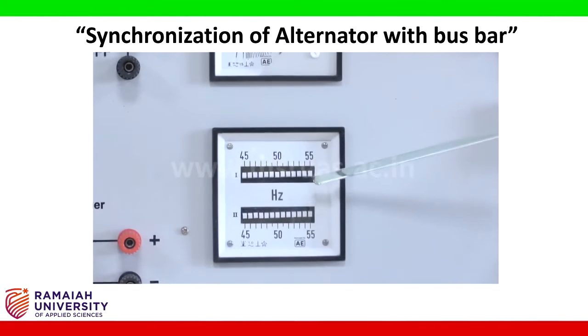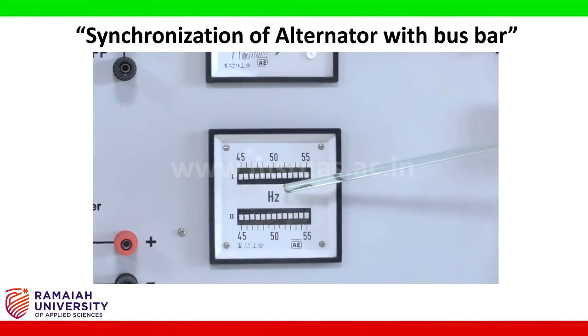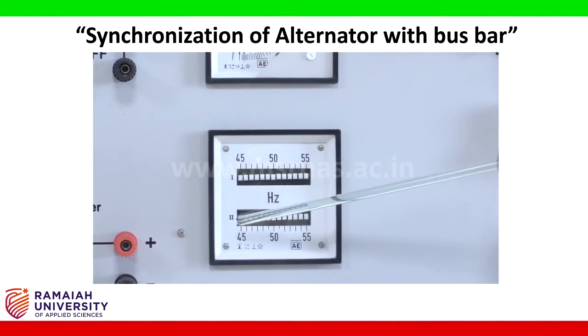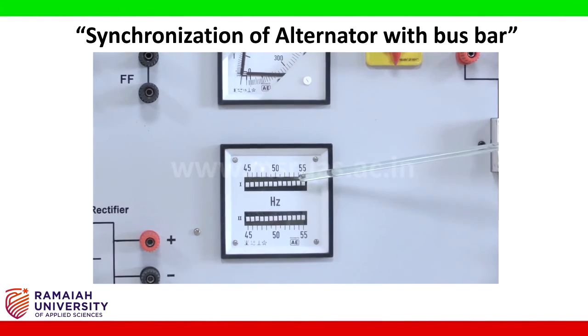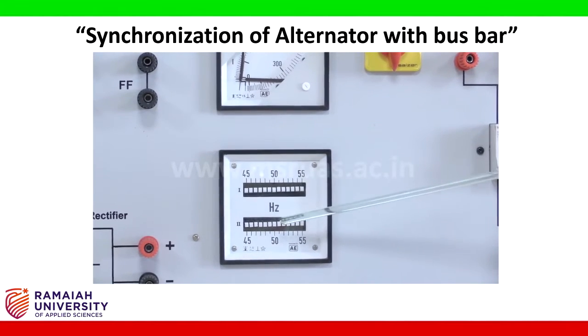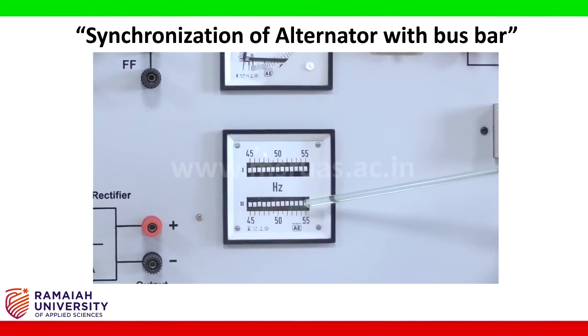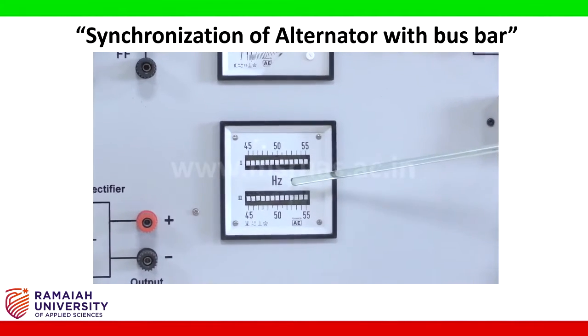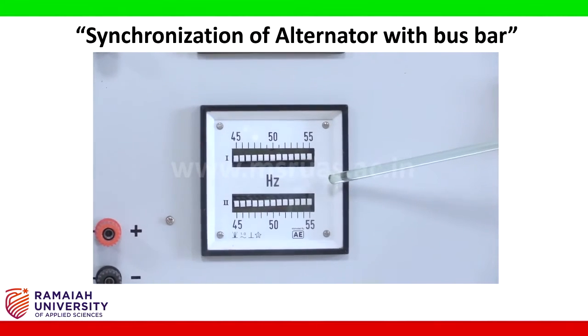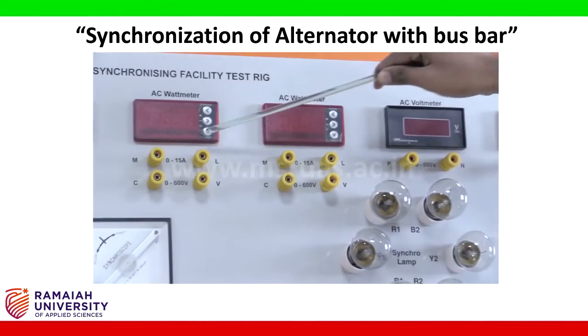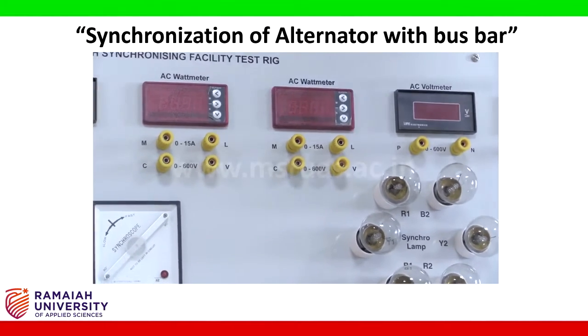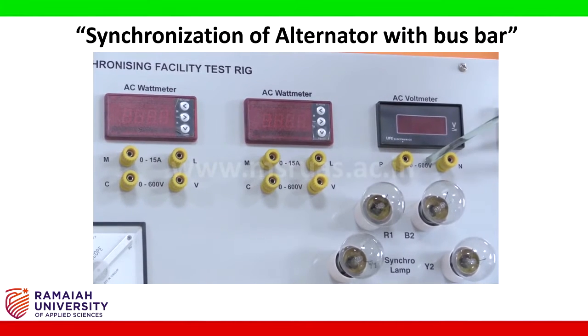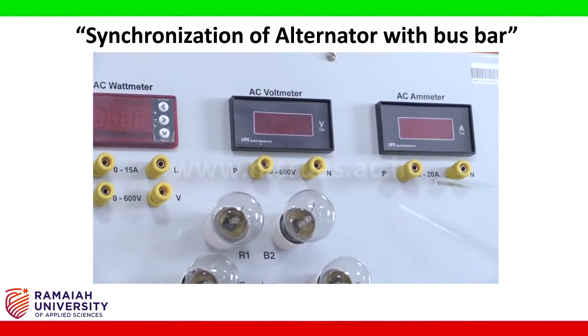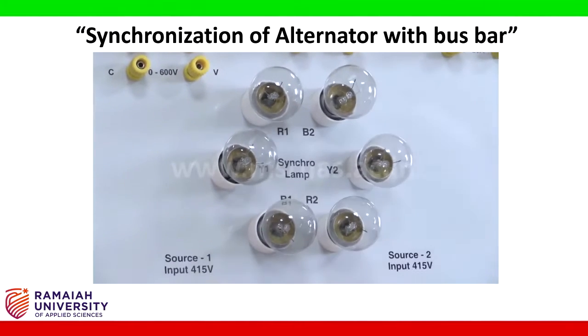This is the very important equipment. This is called reed type frequency meter. If you observe, we are having two frequency scales here. One frequency scale is for the system frequency, the other scale is for our incoming alternator frequency. If both are matched at 50 Hz, we will synchronize our alternator. Along with this, we are having two AC wattmeters of the range 15 amperes by 600 volts, AC voltmeter 0 to 600 volts, AC ammeter 0 to 20 amperes.